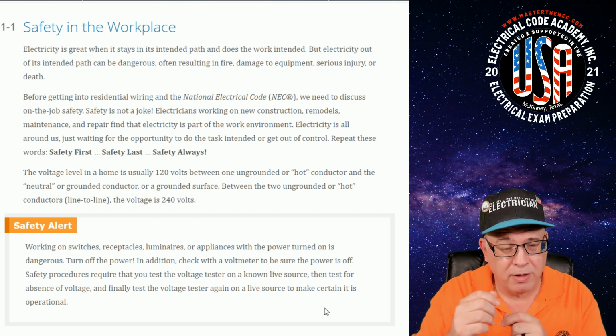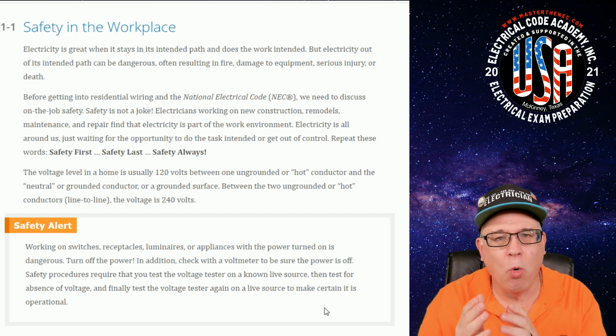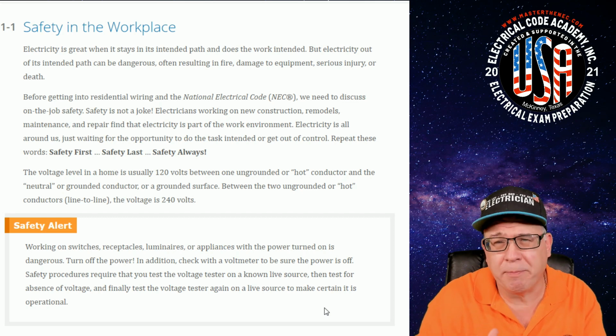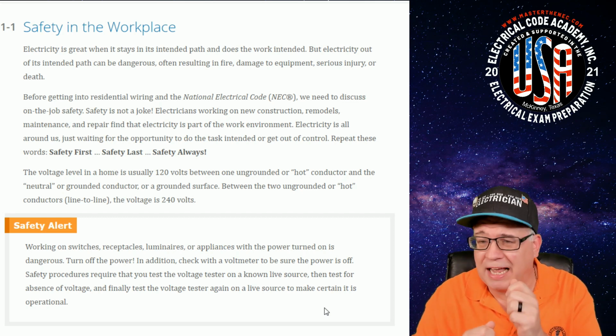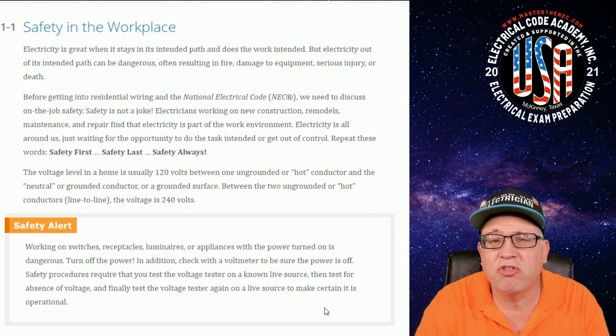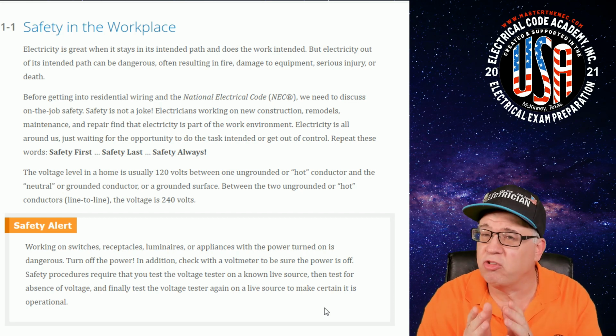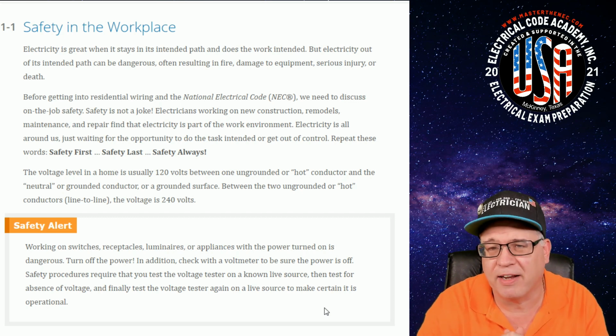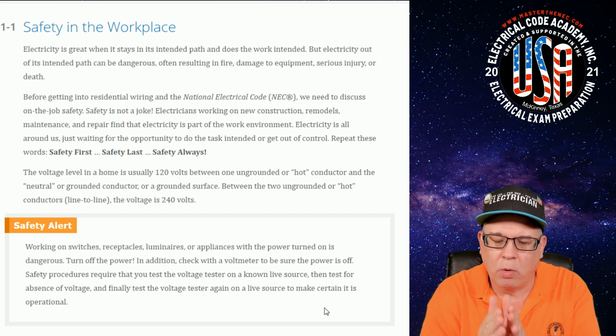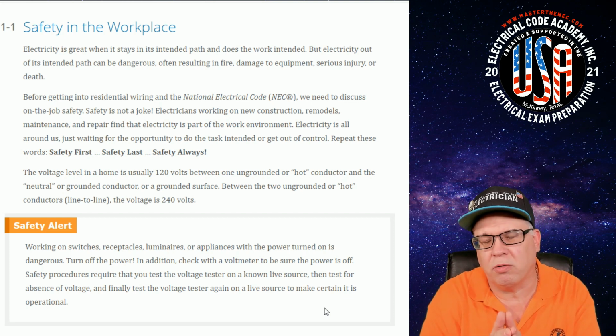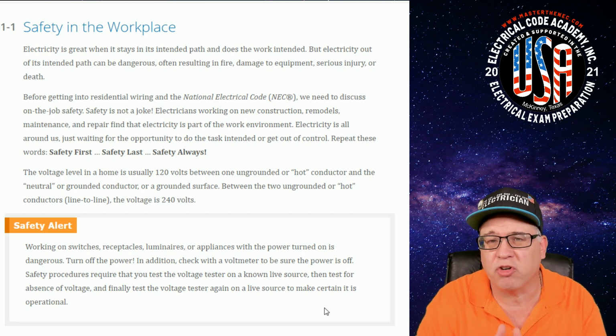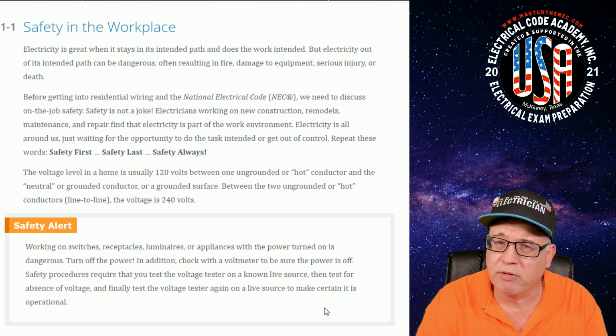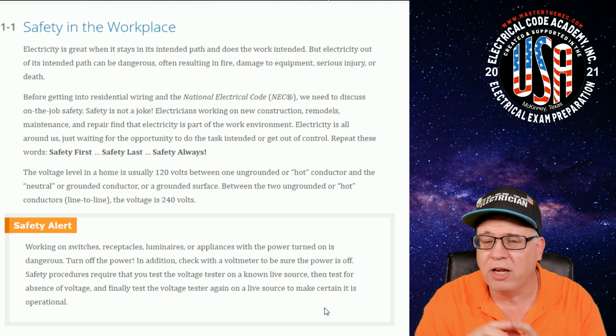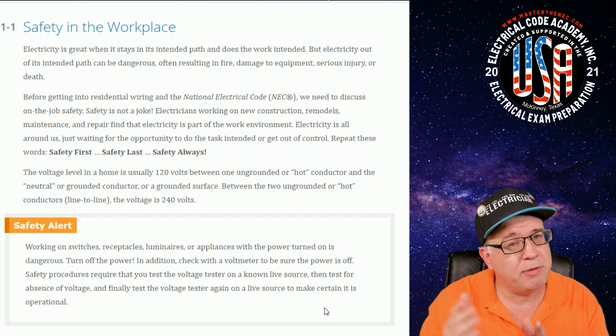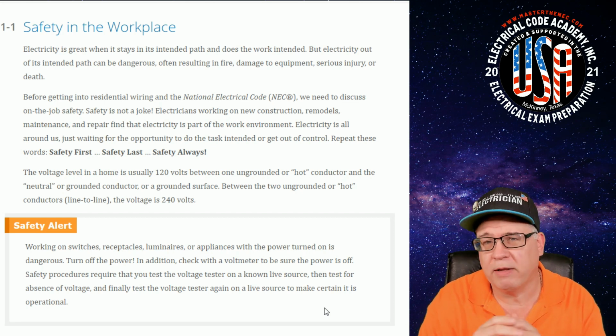If you measure at each end of that winding, or if you're in the panel and put a voltmeter on line 1 and line 2, you get 240 volts of potential because it's utilizing the entire winding of that secondary transformer. The differences of potential are what allow current to flow. But when measuring with voltmeters, remember: line to line is 240 volts, line to neutral or line to grounded metal parts is 120 volts.